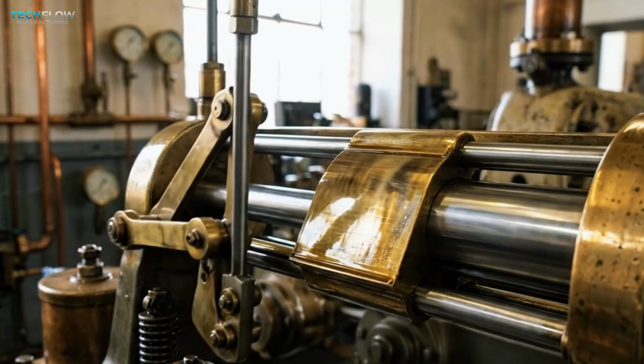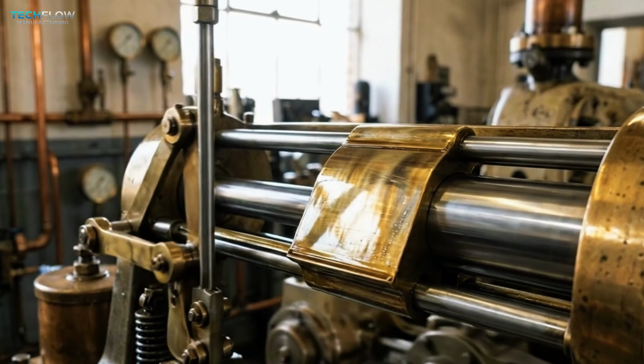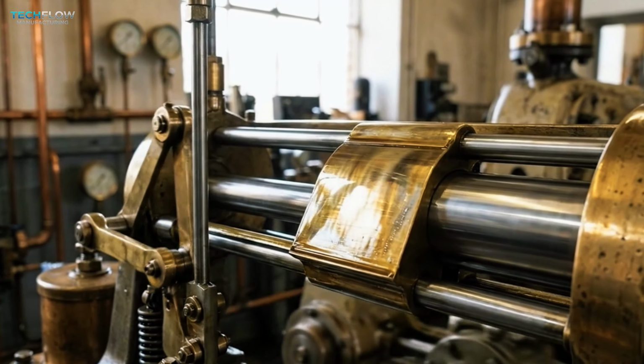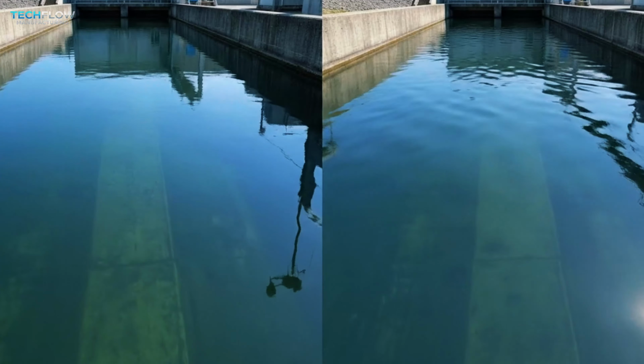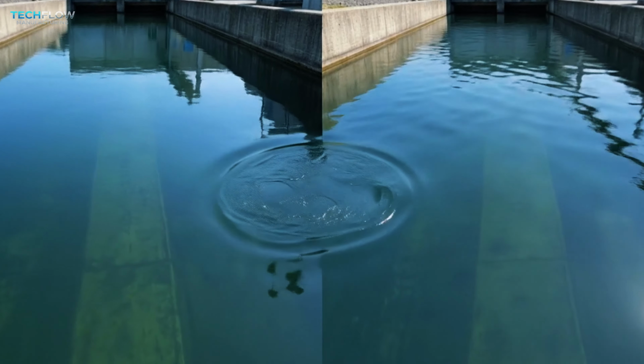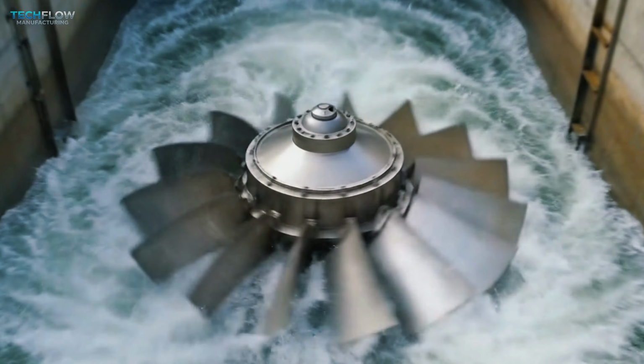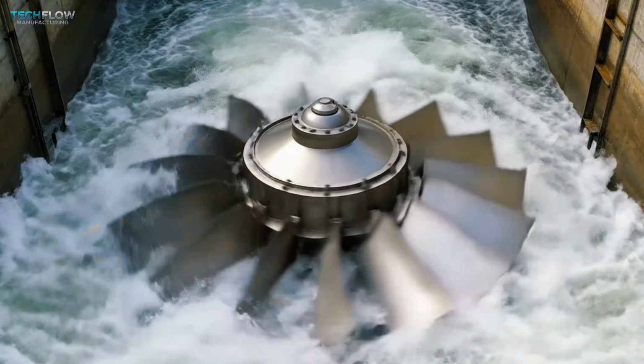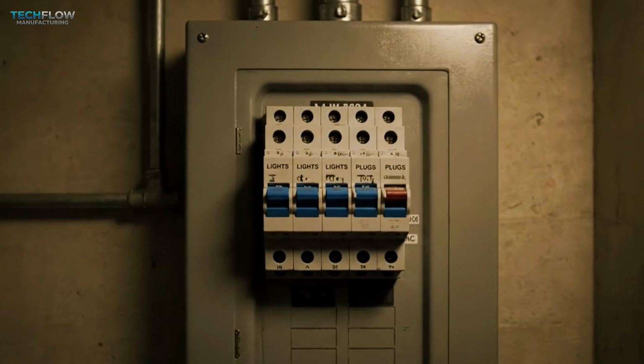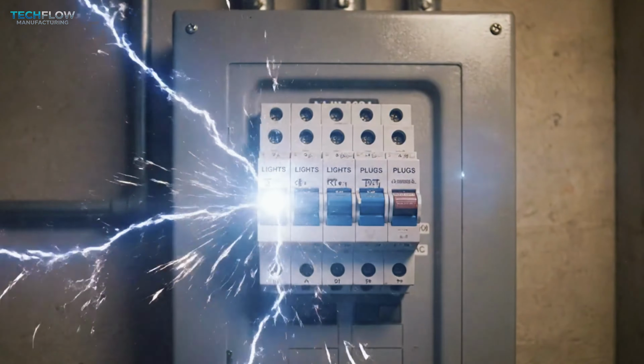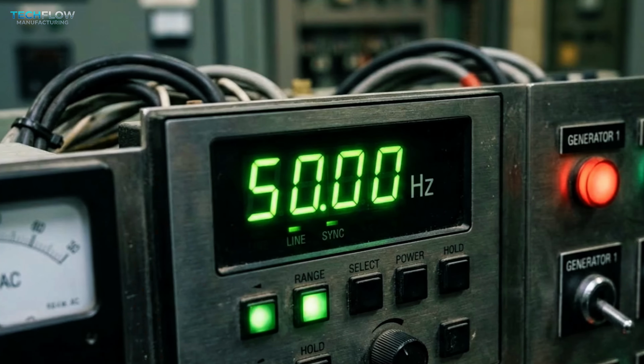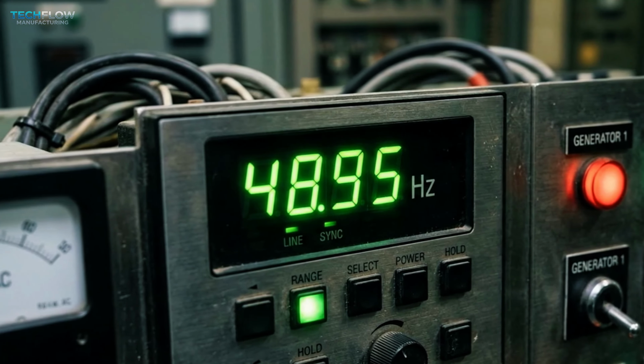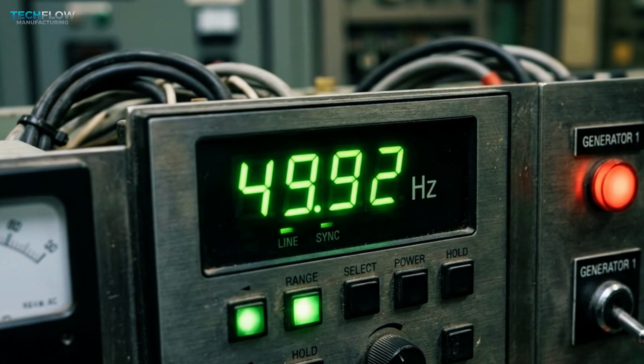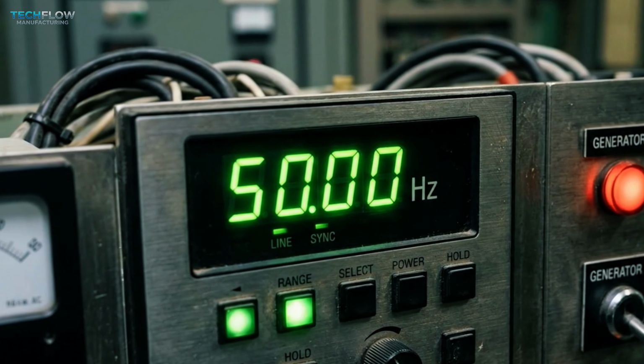The governor system begins to adjust the wicket gates, preparing to synchronize the unit with the national grid. This is the moment of truth, the transition from static potential energy to dynamic kinetic force. Everything is ready. The first kilowatt of Grand Inga power is about to be generated. Synchronization begins. The rotor speed is locked at exactly 50 Hz, matching the heartbeat of the electrical grid.